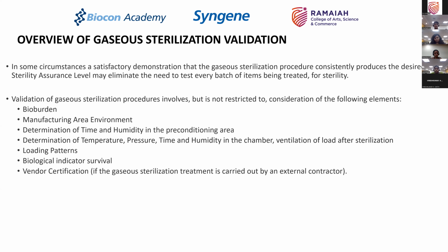So when you carry out a gaseous sterilization procedure, you need to consider all these elements as a part of your process. Just like we did for gamma irradiation, here also determining the initial bioburden, ensuring that the manufacturing area environment is right. If you're doing it in a grade A isolator, you have sealed the isolator properly, there are no leakages.